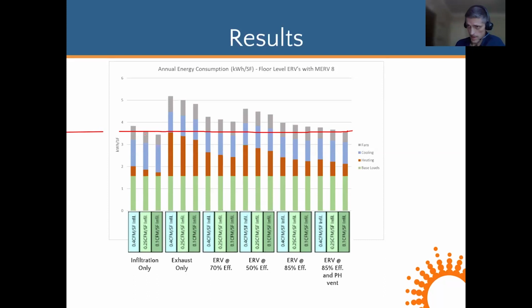So what this tells us here, everything above this line is the penalty of ventilation. That's what we have to bring the air in with fans and then condition that untempered air to the temperature that we want. This is the penalty. And once we get down to passive house level flow rates, high efficiency energy recovery, good airtight building, we can then essentially offset that penalty almost entirely and bring us back down to a case when we didn't bring in any ventilation. That's kind of cool to see.